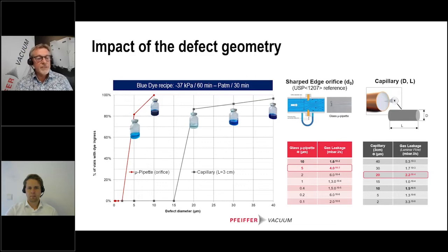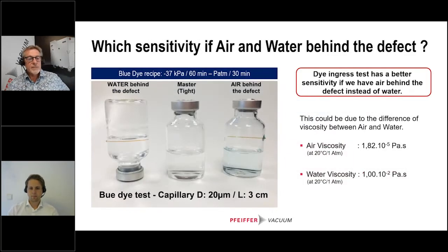So hopefully the physics laws are the same for blue dye and our deterministic method, and you see that the defect geometry has a big impact on the sensitivity of your blue dye test. Another interesting point is the sensitivity if air or water is behind the defect.